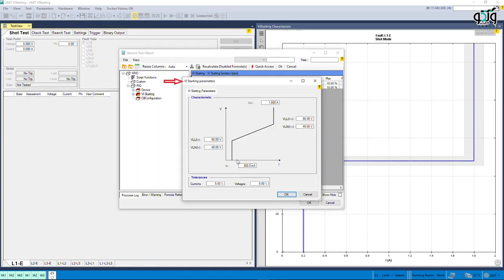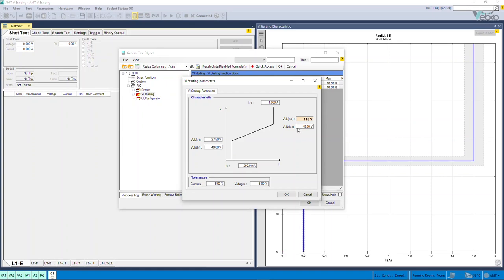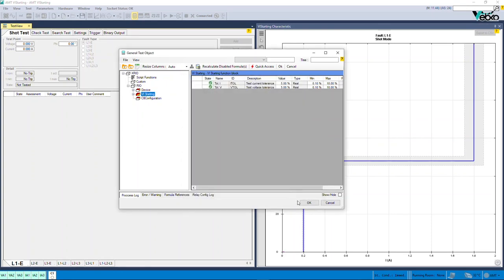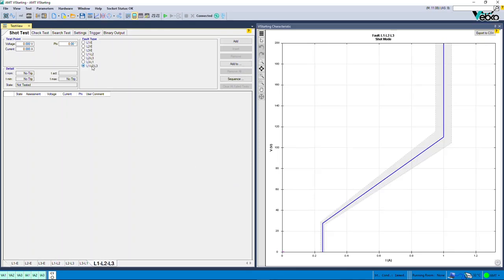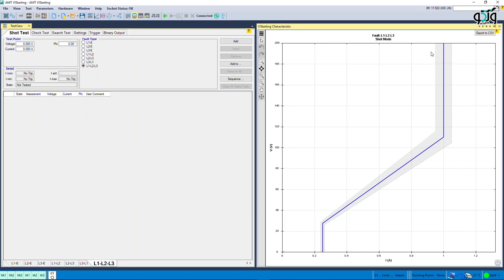In the VI starting parameters page, enter the settings needed to display the VI starting characteristic curve. In the tolerances section, you can also enter the percentage of acceptable fault to perform the test. By confirming the entered settings, it is time to perform the shot test, check test, and search test. In the shot test tab, select the type of fault and points to test; after the test is performed, the evaluation results can be seen. In the check test, the upper and lower tolerances of the relay, displayed as dashes in the VI starting characteristic, are tested and evaluated.